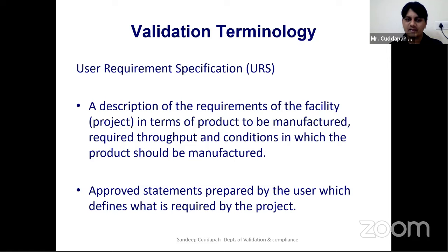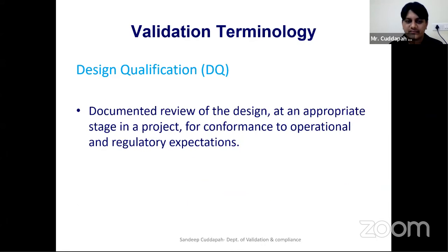So based on your requirements, they prepare the equipment, or they will design those equipments. In the case of design qualification, as I told you, it is verification of your design specifications by the manufacturer against your user requirement specifications, whether they designed as per your requirement or not. That you will verify during design qualification.